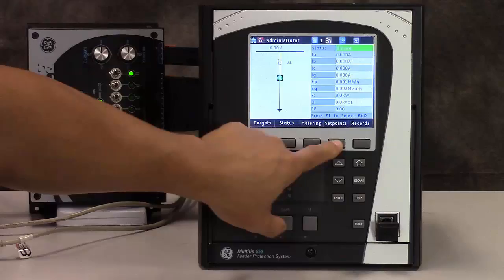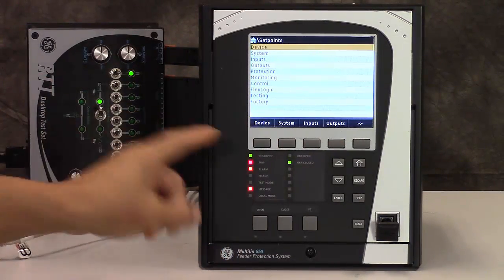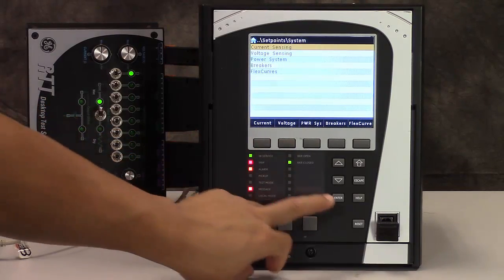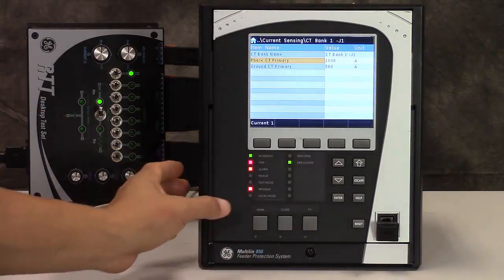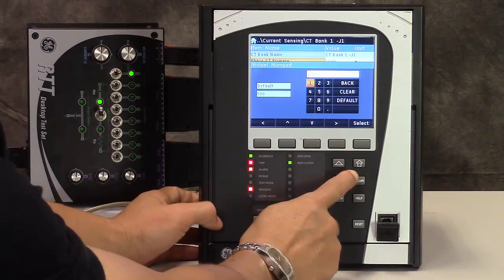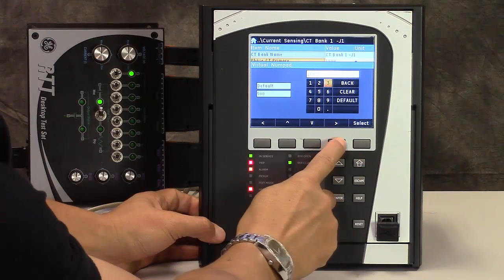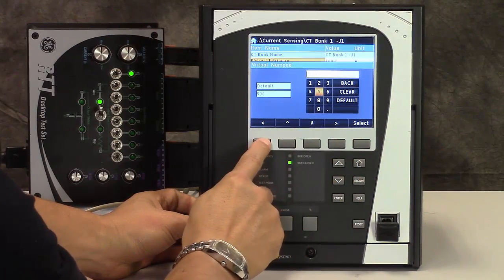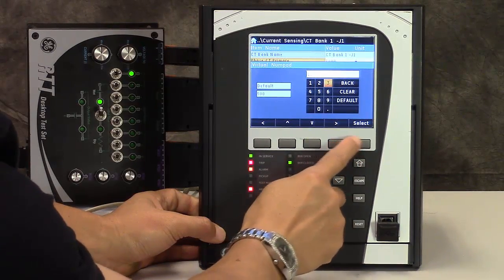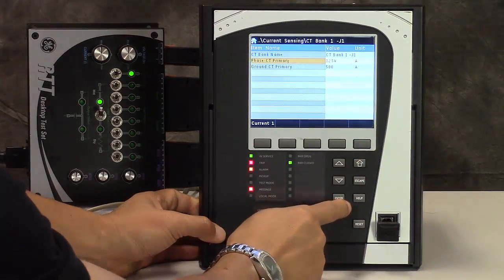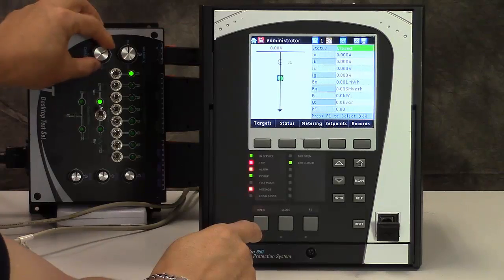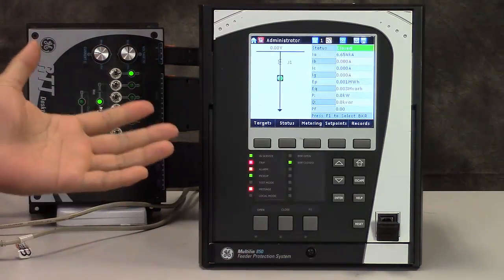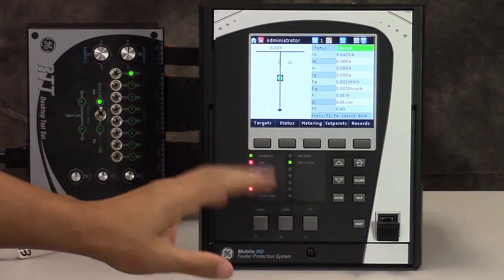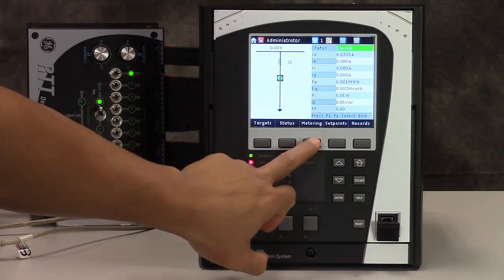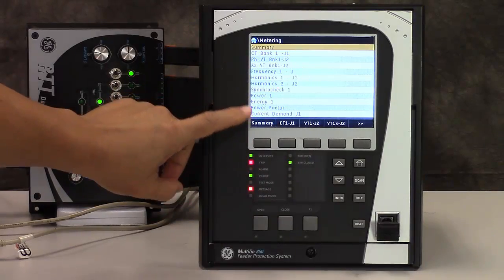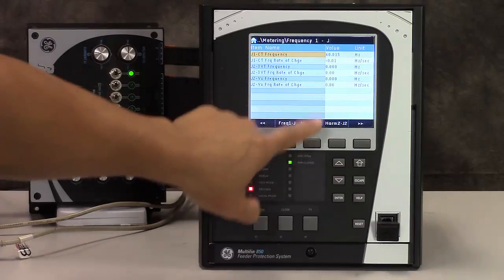And under set points, we can set the basic system setup, for example, the CT primary. So we can enter, let's say for example, 1, 2, 3, 4. Now if I go back and inject single phase current, I'm using these new ratios 1, 2, 3, 4 as my new CT ratios. Then we can check other information such as the VTs, frequency, harmonics.